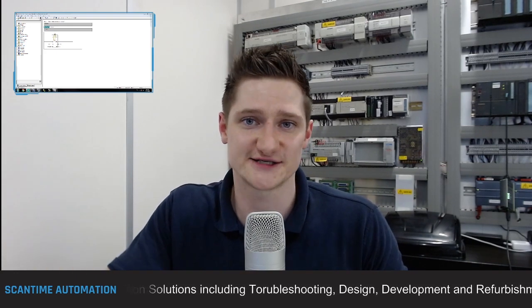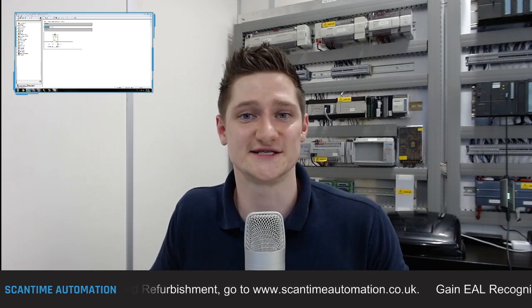If it doesn't, there are things called firmware upgrades which allow your PLC to get the newest software loaded onto it, which may include the new SFBs and SFCs. But it's just something to watch out for. If you don't have the full selection of SFBs and SFCs, it could be the firmware version of your PLC is slightly outdated, it's no longer the newest version going. And that there is system function blocks inside of the STEP7 PLC.